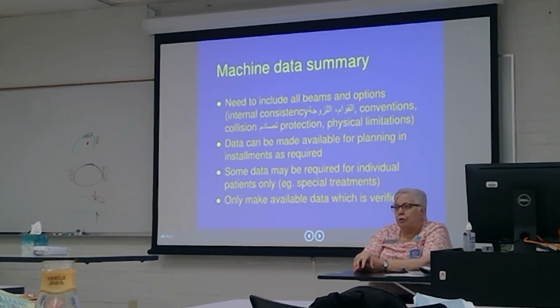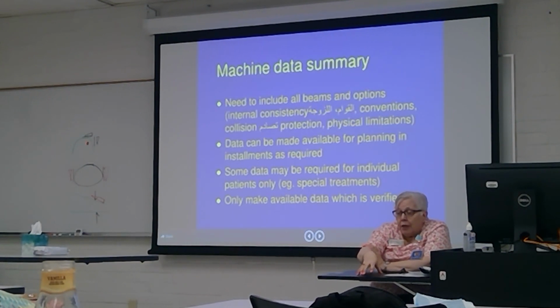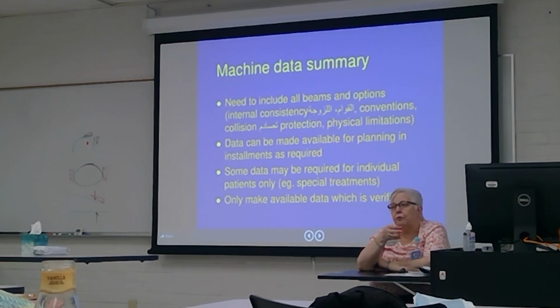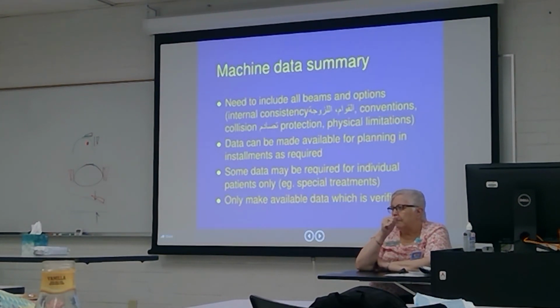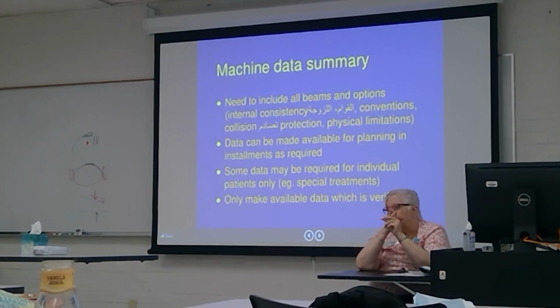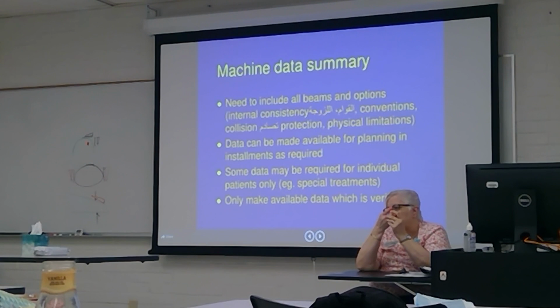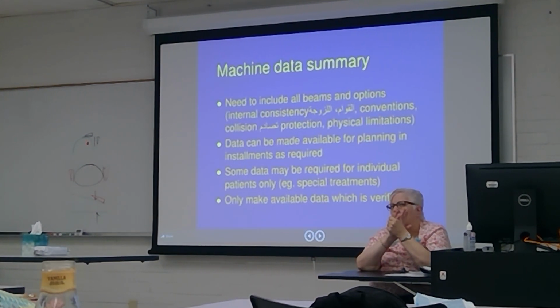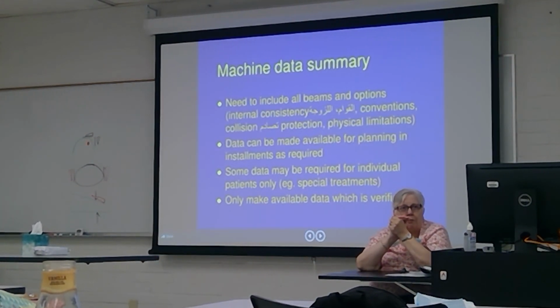You have to make sure, if you are doing a plan or you're checking a plan, which you have to do on the treatment machine before it starts, that everything is verified. So you don't start a plan which is not verified. And that includes signatures from everybody involved. The dosimetrist, the physicist, the doctor. And don't take a phone call saying, yeah, I'm okay with it, you can go ahead and continue.